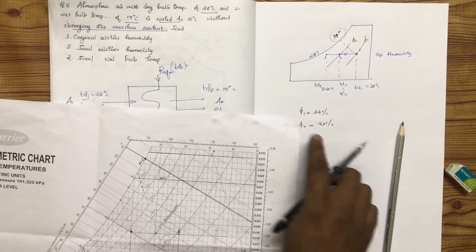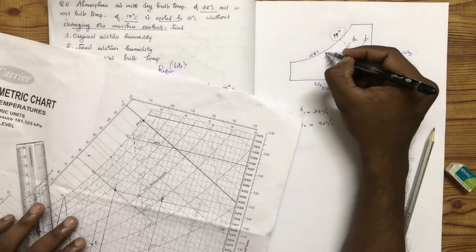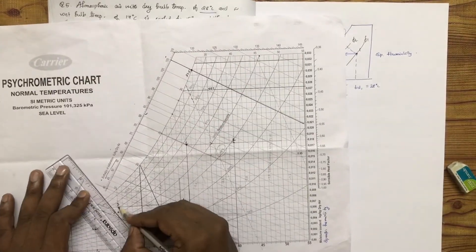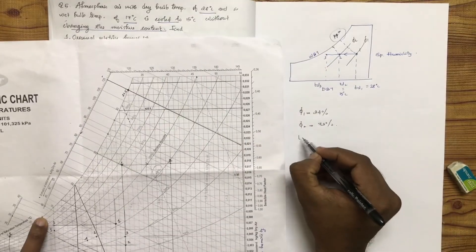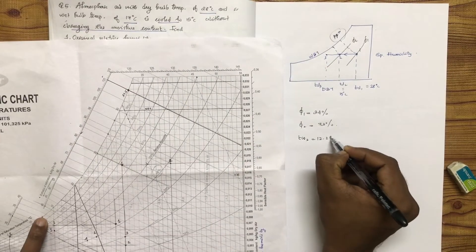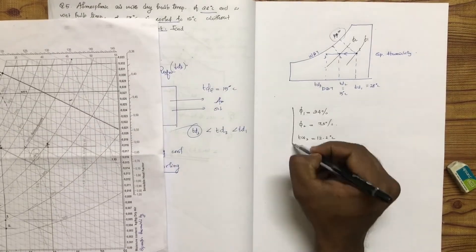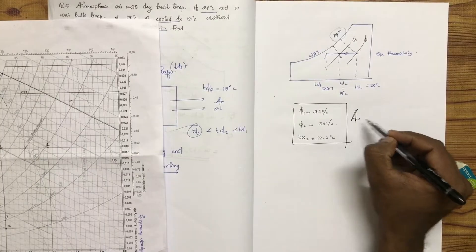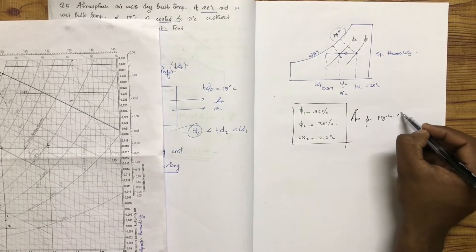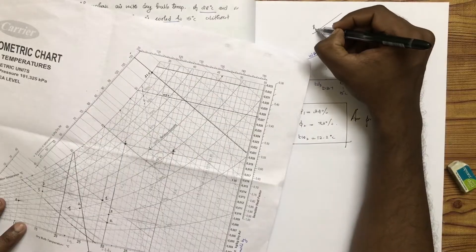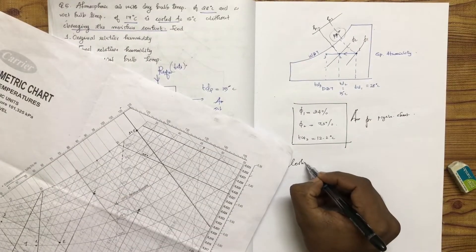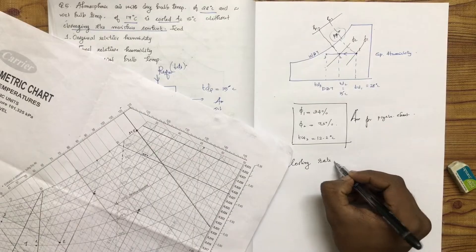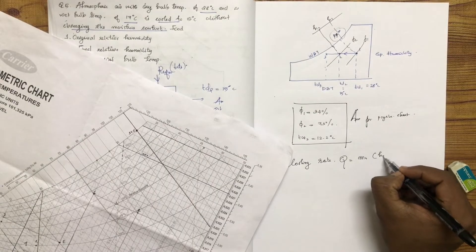The final wet bulb temperature TW2, which is equal to 12.2 degrees Celsius, is read from the psychrometric chart. Moving on, we will discuss the sensible cooling heat rate. The cooling rate is q equals ma into h2 minus h1, where we find H1 and H2 from the chart.